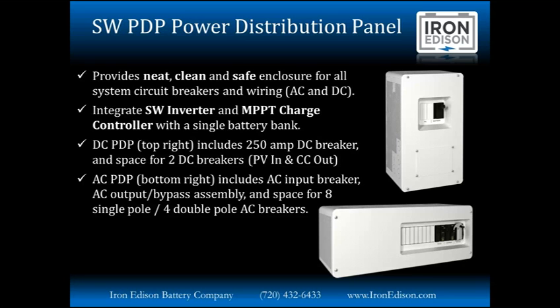Included in it, the DC power distribution panel up on the top right comes with a 250 amp breaker for the battery to inverter connection, as well as two additional spaces, as you can see there, for the input and output breakers for your charge controller, PV input and charge controller output to the battery. The AC power distribution panel there at the bottom includes an AC input breaker for whatever that input source may be, grid or generator, as well as the output bypass assembly for the output of the system, as well as additional space for 8 single pole or 4 double pole AC breakers.